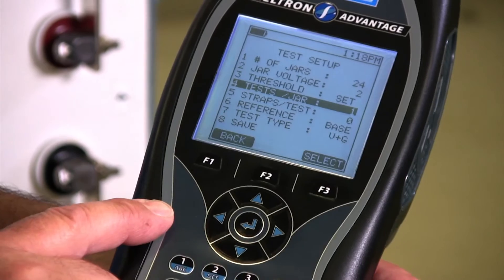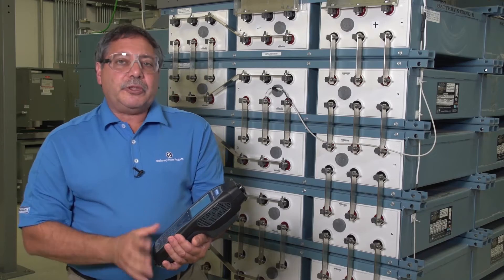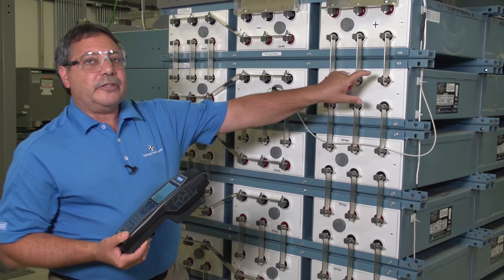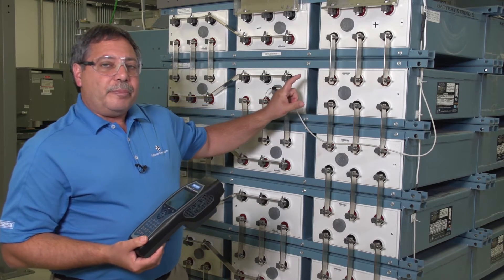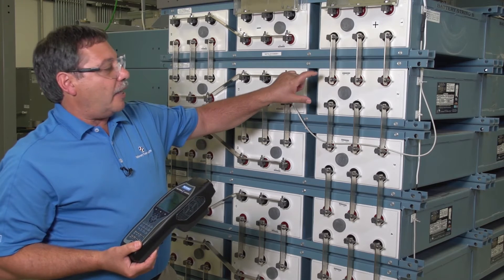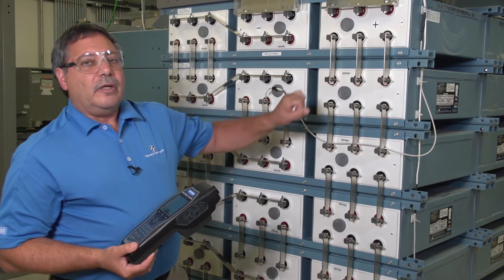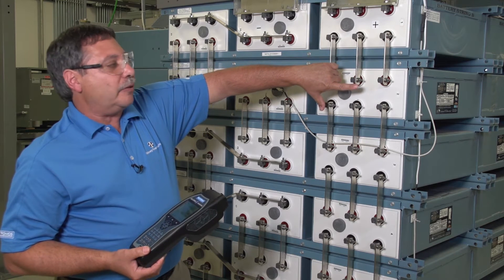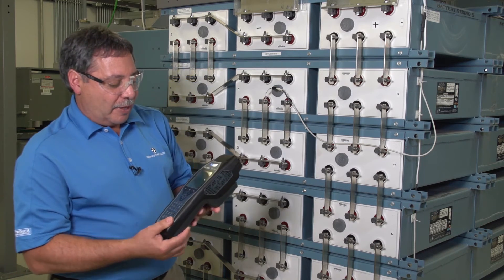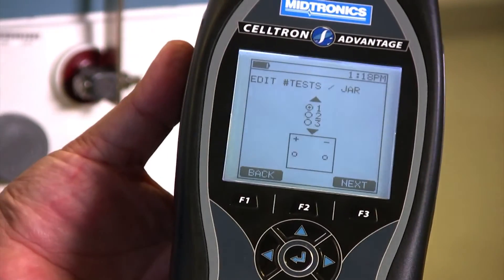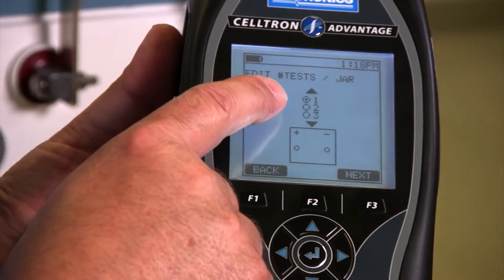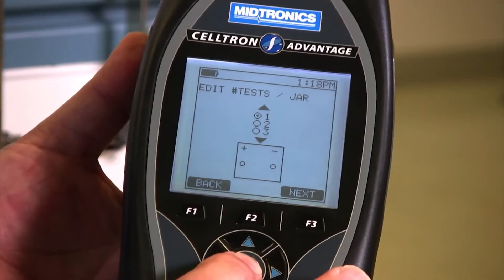Next is going to be test per jar. So test per jar is telling me, in a situation like this where I have three sets of posts, some companies' policy is to test on each set of posts. Other people just make one test across this cell and maybe only do one test per jar. So you have that option if you drill into this menu to do one, two, or three tests per jar, per cell. We're going to keep it here to just do one test.